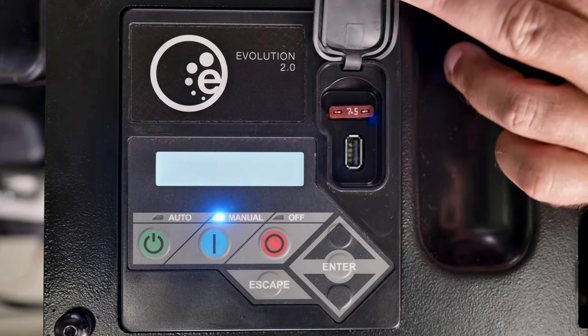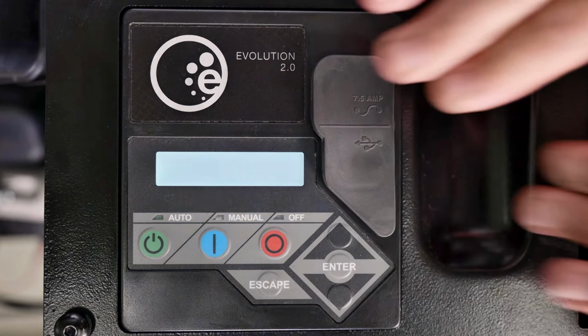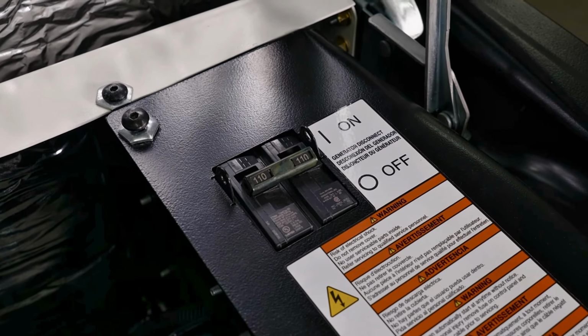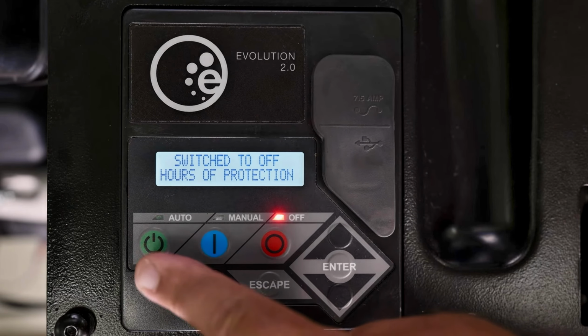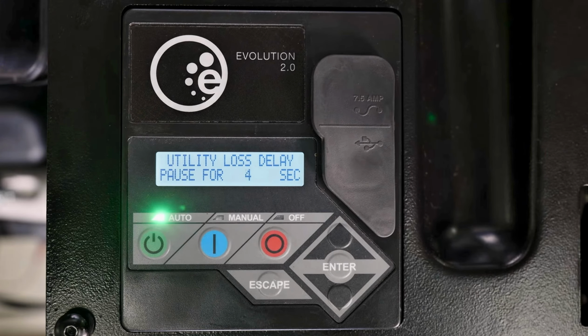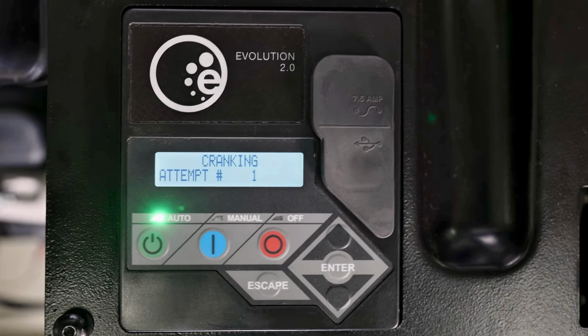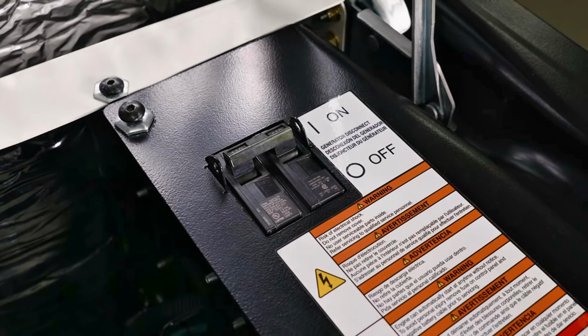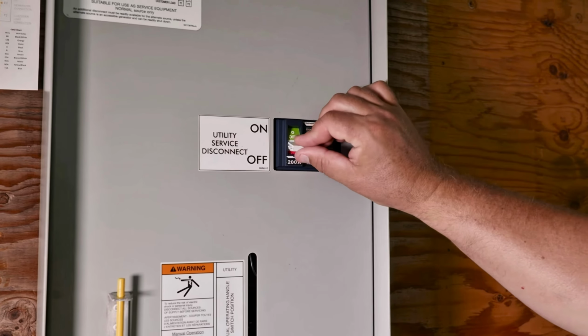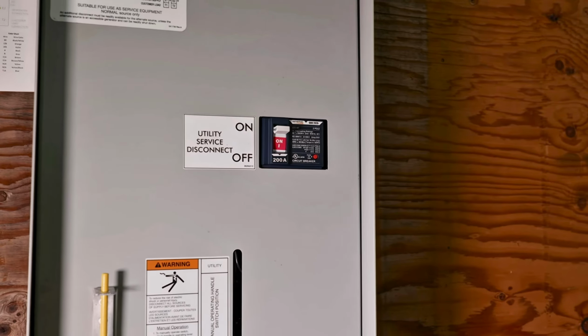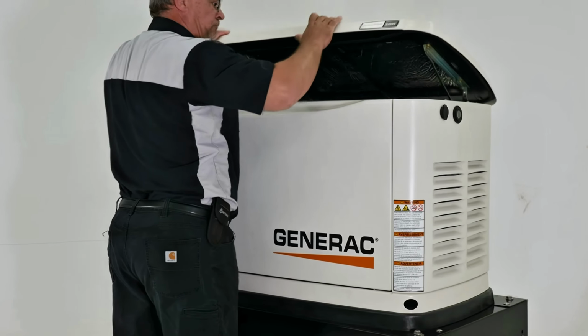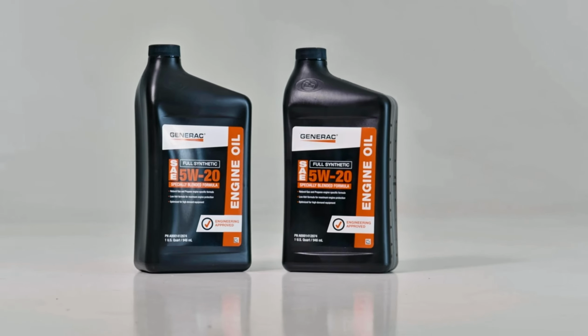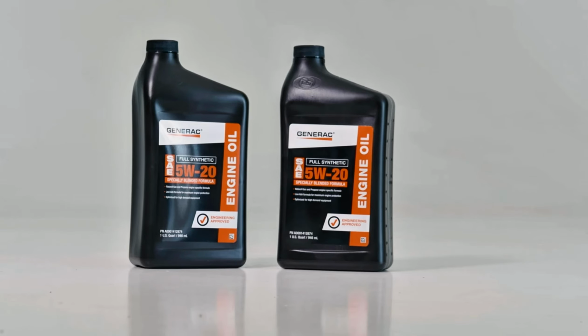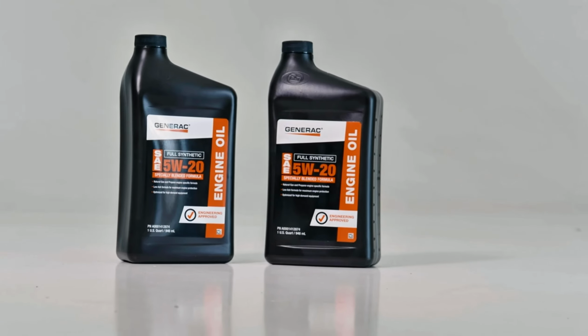If the generator has been running because of an outage, you will need to first reinstall the 7.5 amp fuse. Then verify the generator's mainline circuit breaker is still off, and press the auto button. Allow the generator to crank, start, and run to warm up for 1 to 2 minutes. Then turn the generator's mainline circuit breaker to the on position and turn the utility mainline circuit breaker to the on position. The generator is now fully operational and powering the load. Be sure to dispose of the used oil and oil filter in accordance with national, state, or local codes.